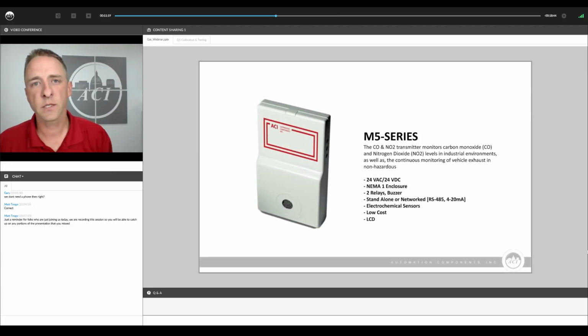Moving on to our toxic and combustible gas sensors. The M5 series is our baseline of toxic or combustible gases, commonly CO and NO2. This is a small, inexpensive, sleek wall mount gas sensor that's available with an analog output, or you can get relays and an LCD display on this package as well. It's low cost, it uses an electrochemical sensor, and it has the option to include relays and an audible buzzer alarm built right into the enclosure.